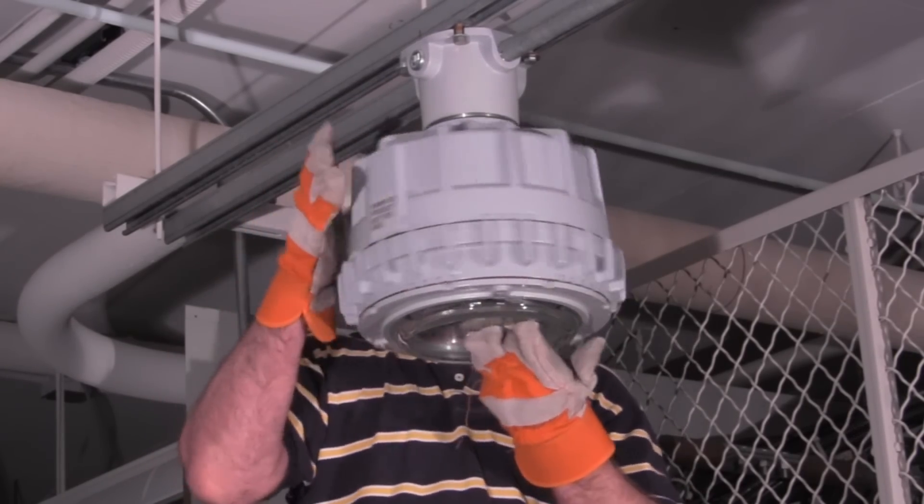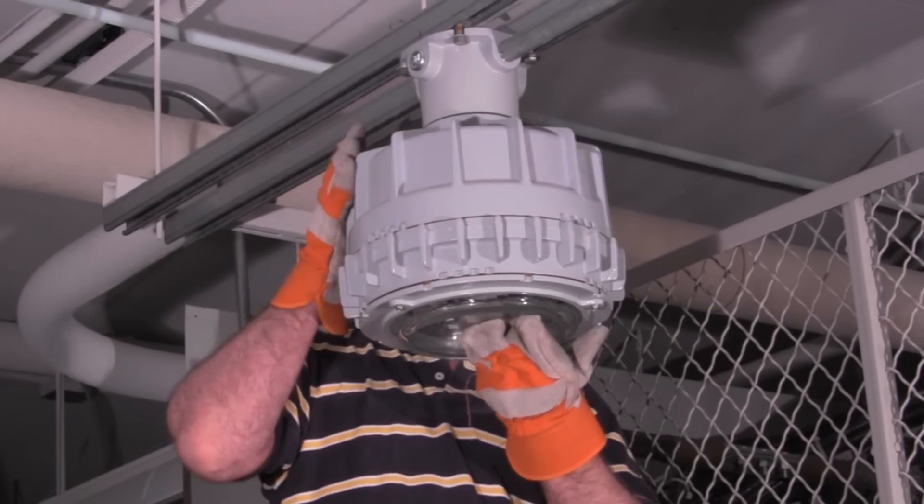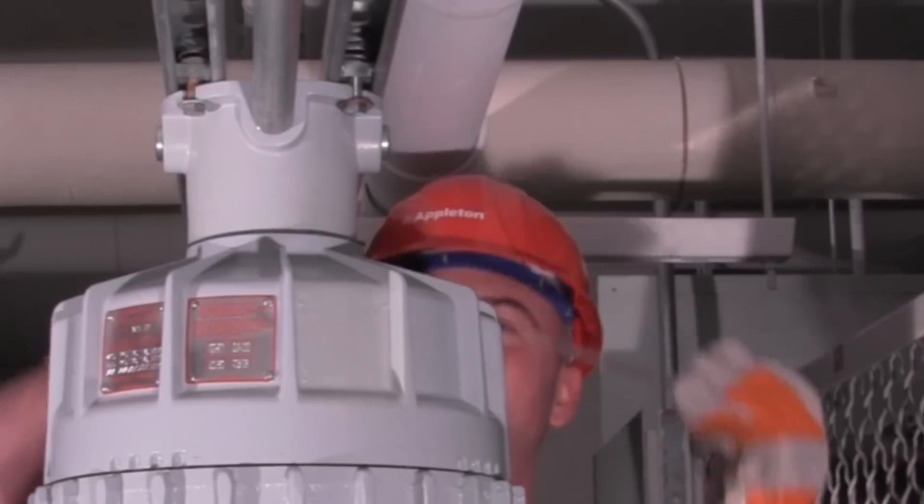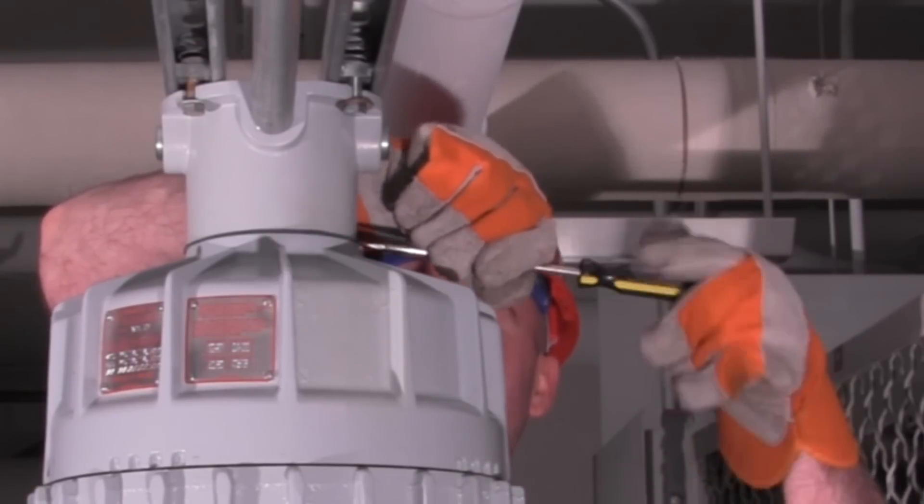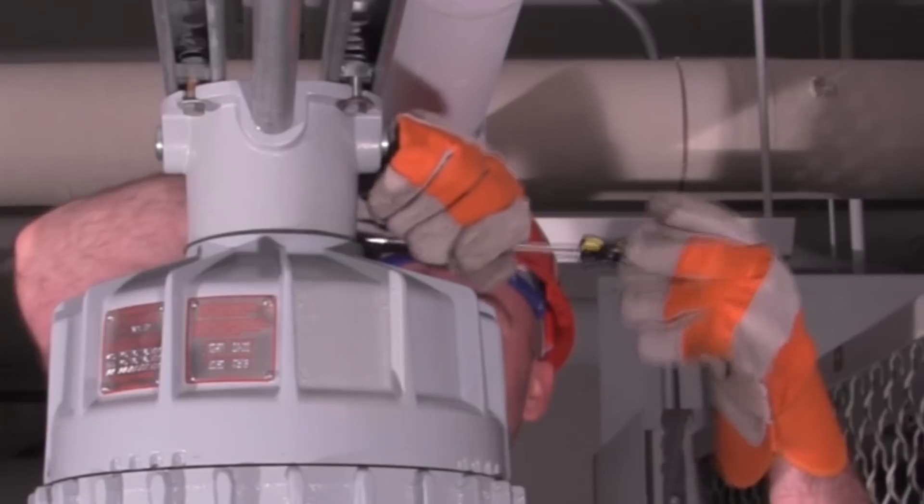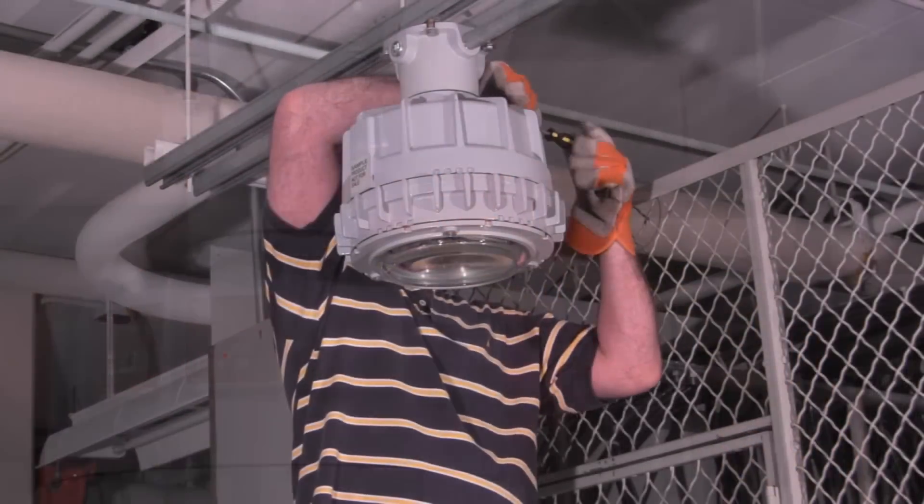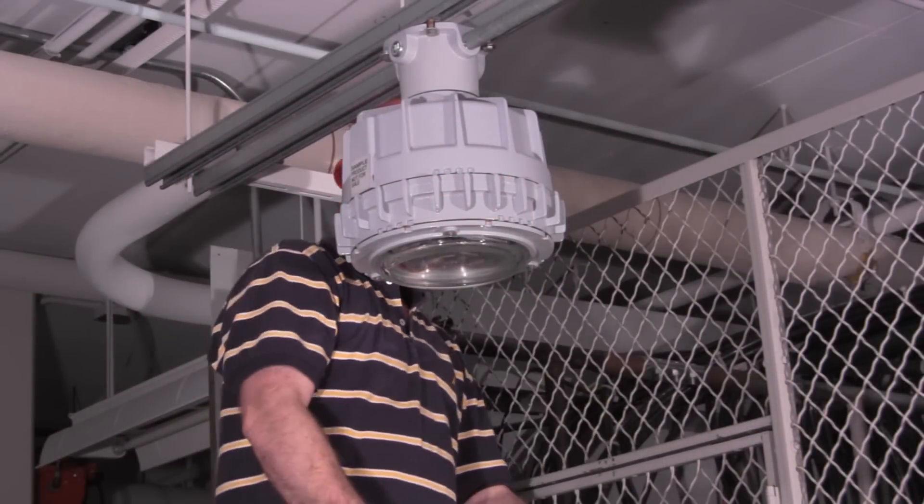Ensure that the fixture is threaded securely. Then tighten the locking set screw on the existing mounting hood. Once the new fixture is properly threaded and seated in the mounting hood, electrical contact will automatically engage. Therefore, there is no need to rewire to change Codemaster lighting fixtures.